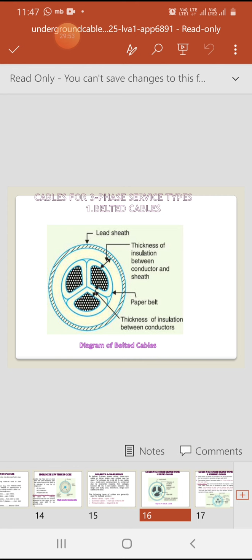Now I want to discuss belted cables. See the diagram of belted cables. First three conductors, then above that some insulation we are providing between the conductors. Then after that paper belt is used. Then the next one is insulation between conductors and sheaths. Then finally we are giving lead sheath, and above that obviously other parts which we previously discussed. Normally belted cables are used for voltage up to 11 kV, and it may be extended up to 22 kV.